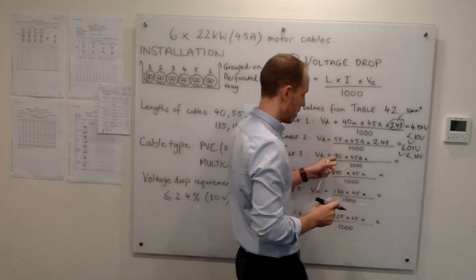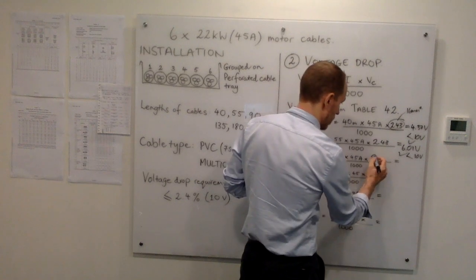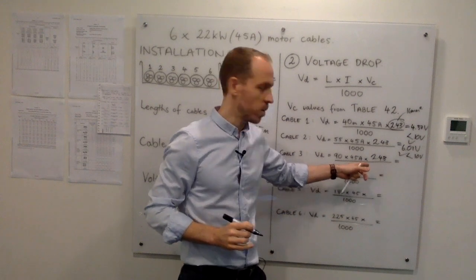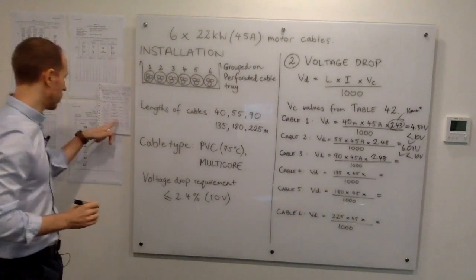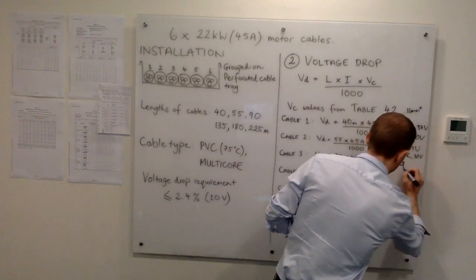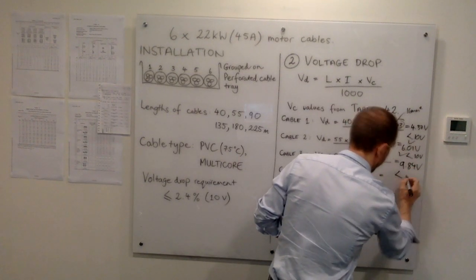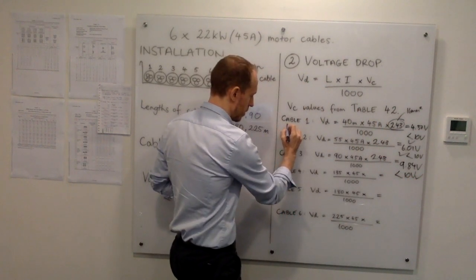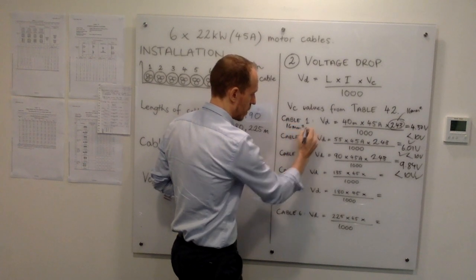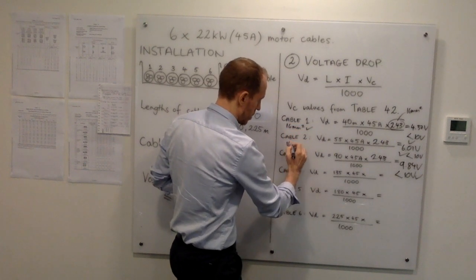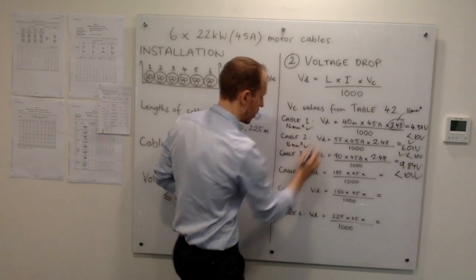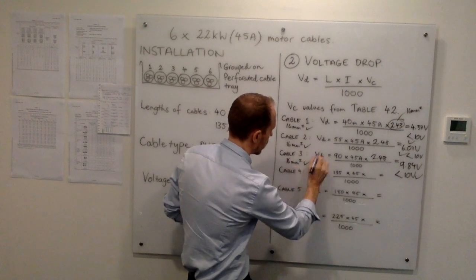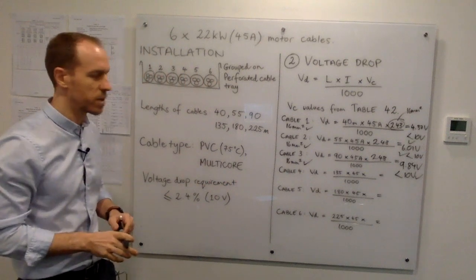Cable 3 is 90 metres at 45 amps. Using the VC value for a 16mm² cable, the voltage drop works out to be 9.84 volts, which is still less than 10 volts. So 16mm² is fine for cables 1, 2, and 3.